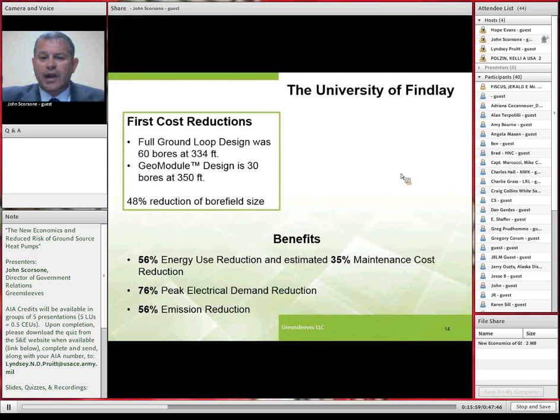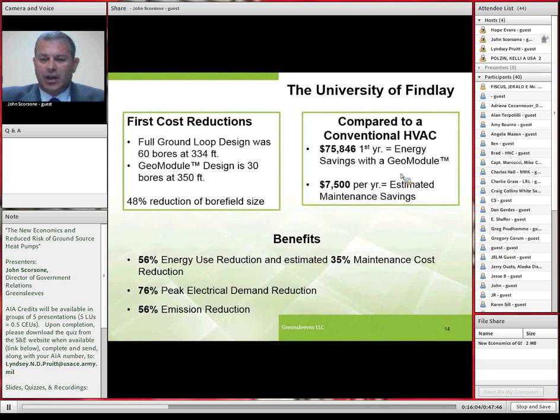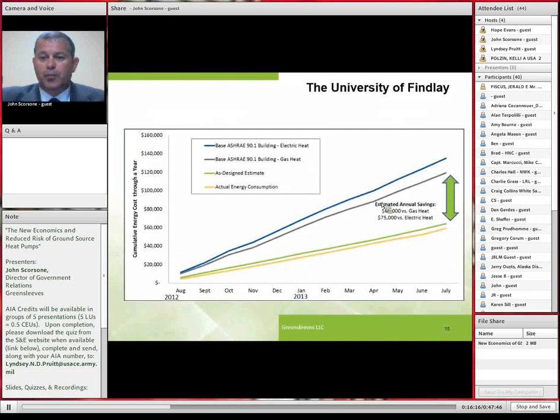The blue line represents the actual energy cost of operating a traditional ASHRAE HVAC design with electric heat. The gray line is the same ASHRAE design with gas heat. We predicted the GeoModule would provide the green line level of savings. The actual results are shown by the yellow line. So a significant reduction from what we predicted.